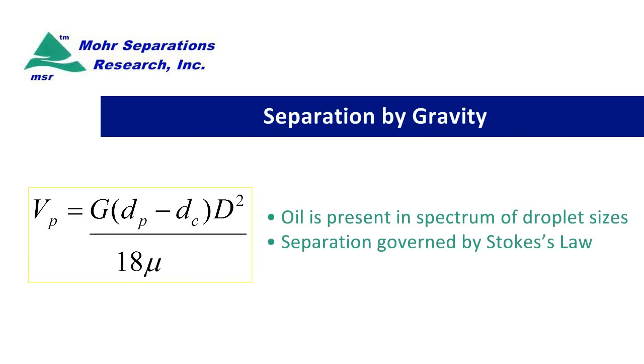So this is Stokes Law here. The oil is present in a spectrum of droplet sizes from some very tiny ones to some quite large ones, and the separation of the oil in any kind of separator, be it an API separator or a coalescing plate separator, is governed by Stokes Law.